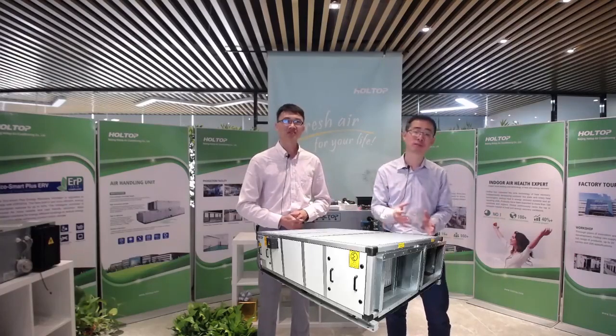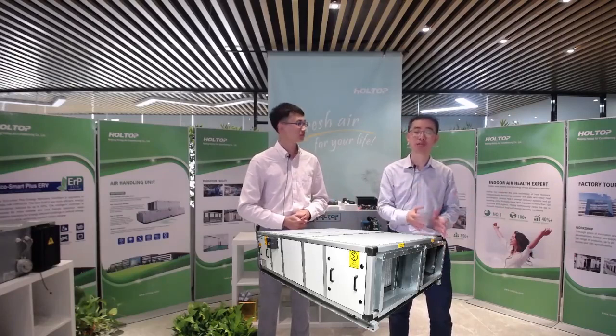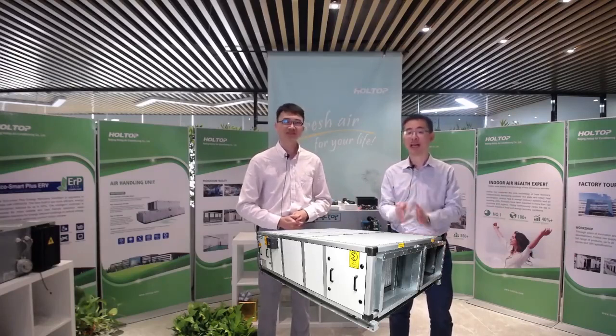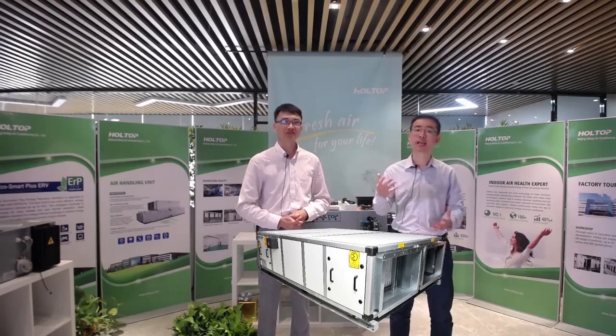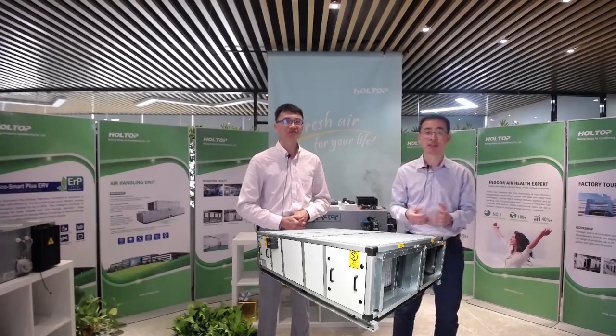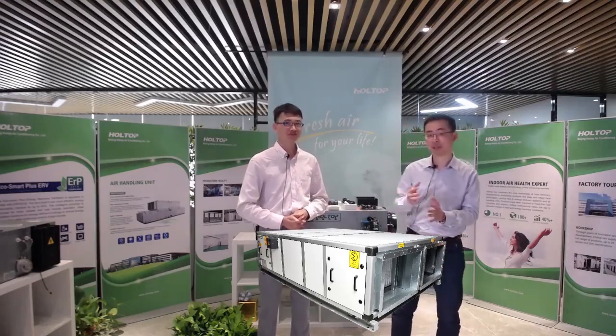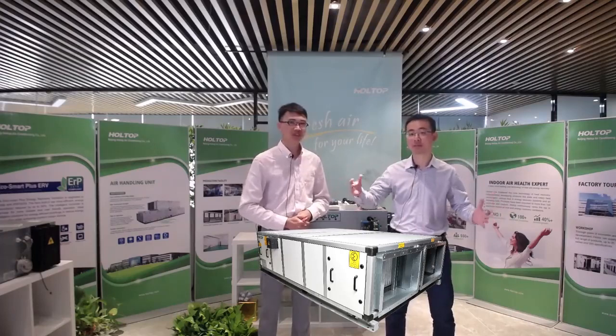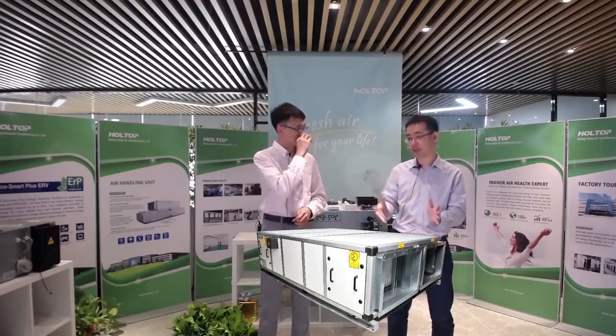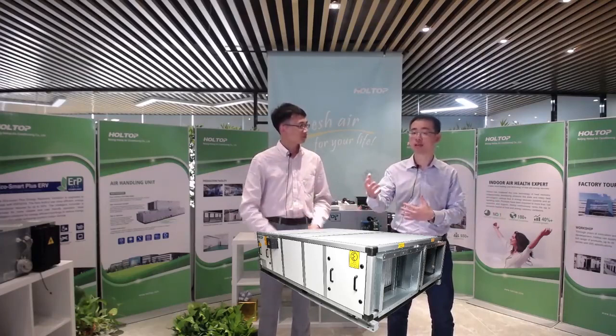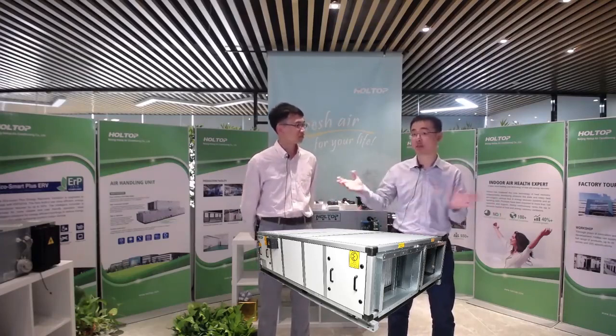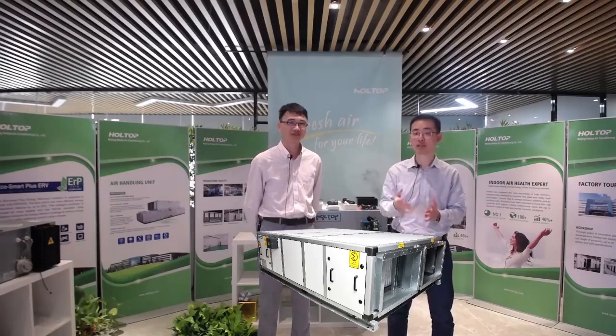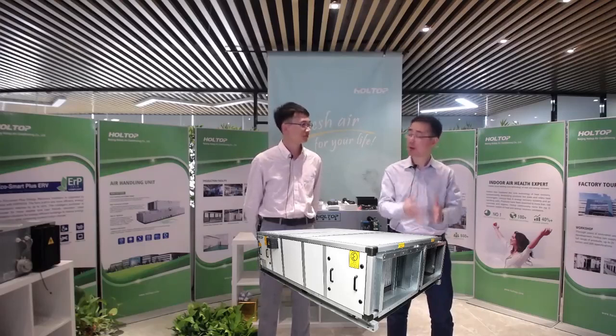And the airflow is from 2,400 cmh to 8,500 cmh, and they can have three-speed air regulation. At the same time, because it has a different type, we're thinking about the application in the future. It will have long ducts for each project. So our external static pressure can be 100 to 300 Pascal.